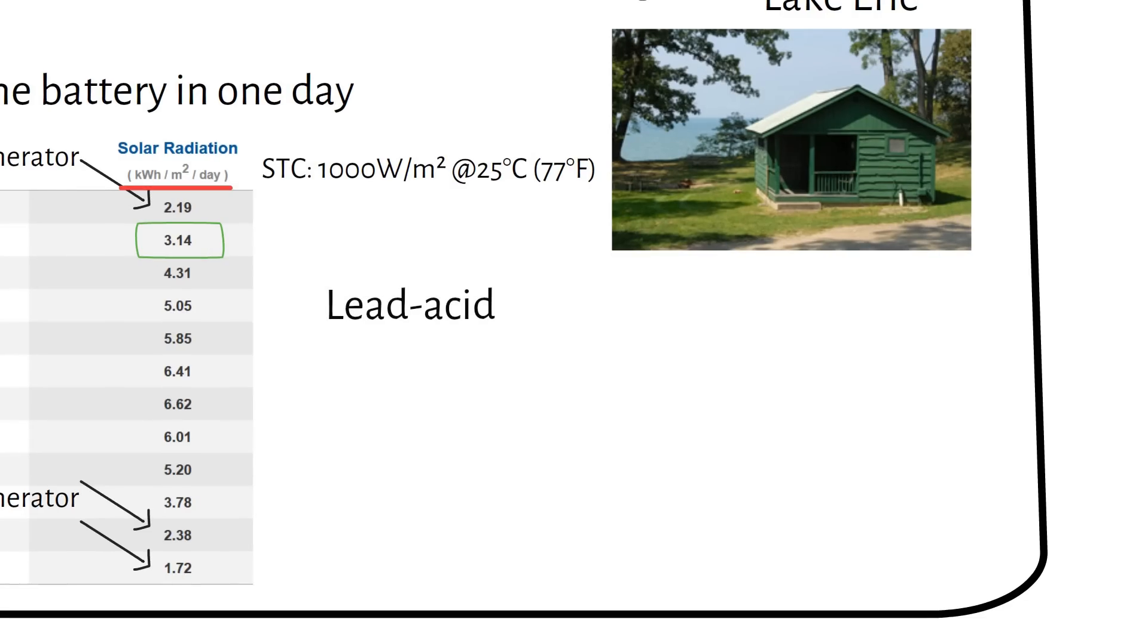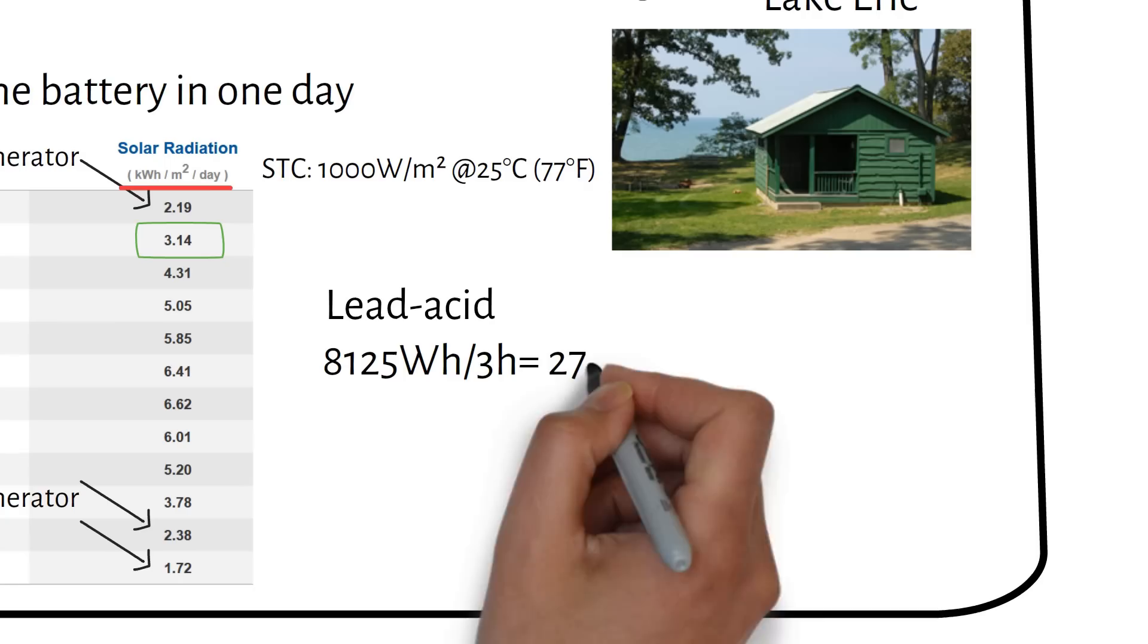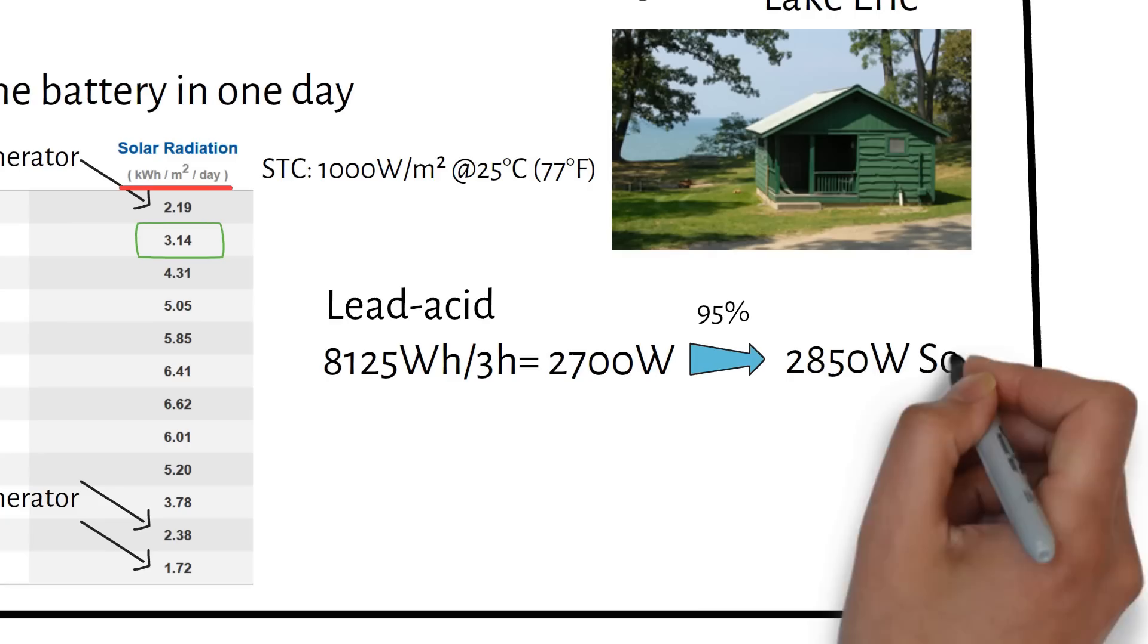To recharge a lead-acid battery from 50 to 100% we needed 8125 watt hours. With 3 sun hours this becomes a total of 2700 watts. Then, divided by the charge controller efficiency of 95% we become 2850 watts of solar panels.